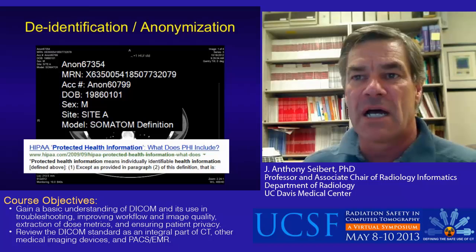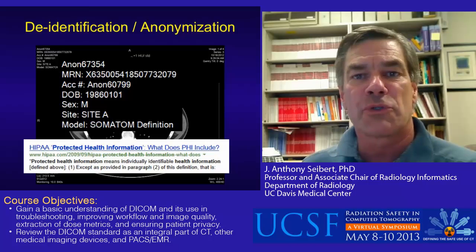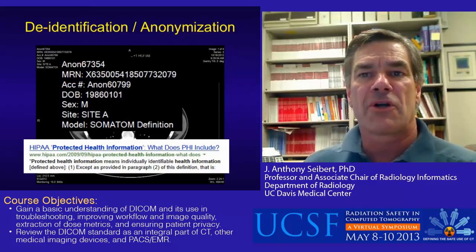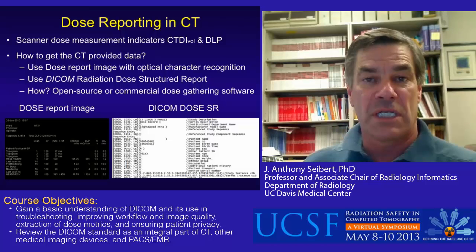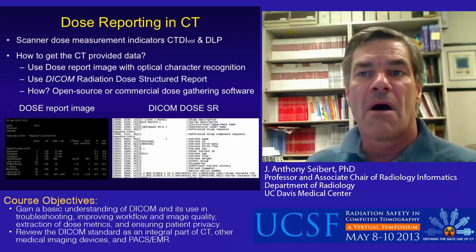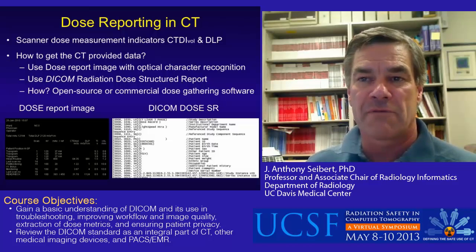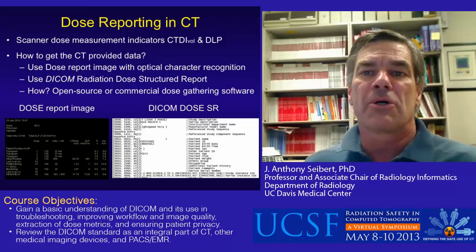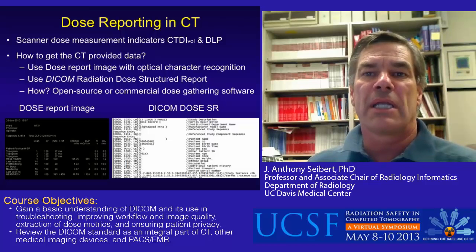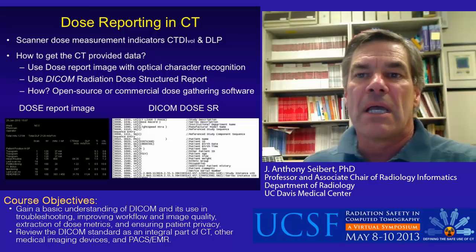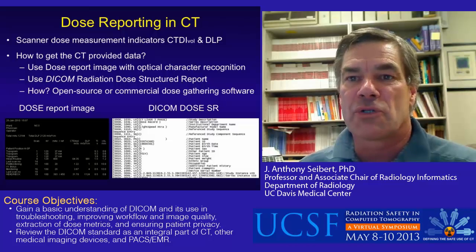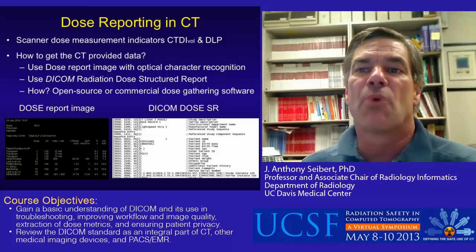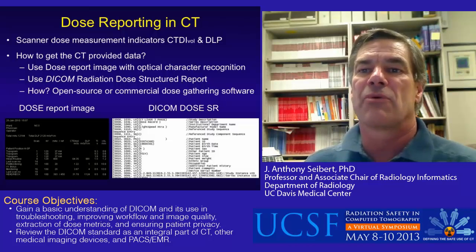Another very important aspect of DICOM, particularly pertinent to this virtual symposium, is the dose reporting capabilities that are part of the DICOM standard. For CT, the dose metrics — Computed Tomography Dose Index, CTDI-VOL, and Dose Length Product, DLP — are required to be reported in the interpretive diagnostic report of the patient in the state of California. Until recently, the typical method of getting dose information was by creating an image of the dose report and placing it with the CT scanner generated images. The Radiation Dose Structured Report, RDSR, provides more complete and formatted information about the dose metrics and relevant acquisition parameters.